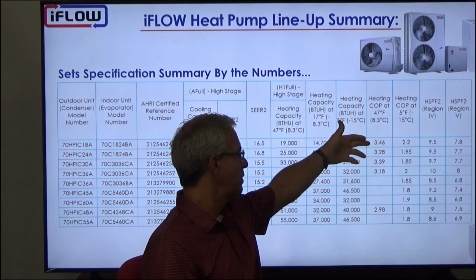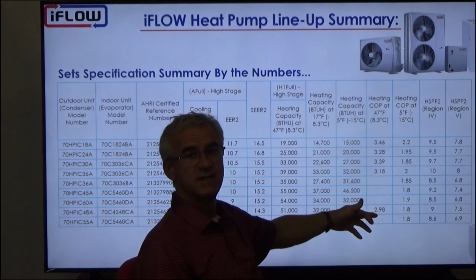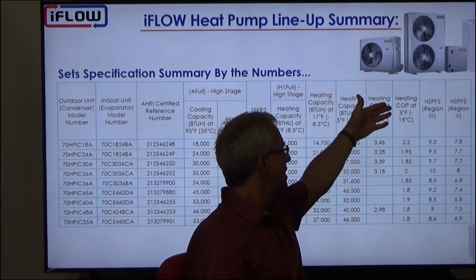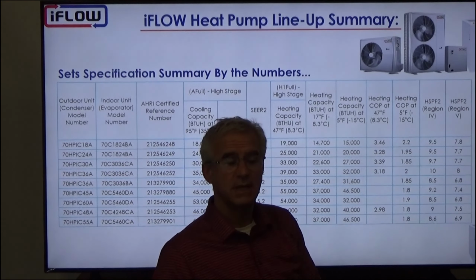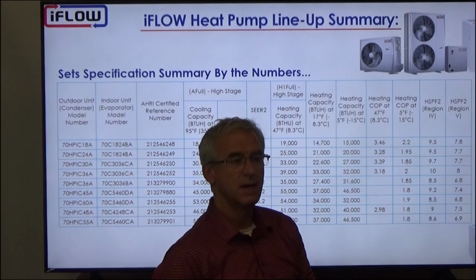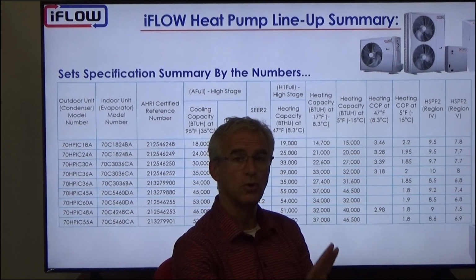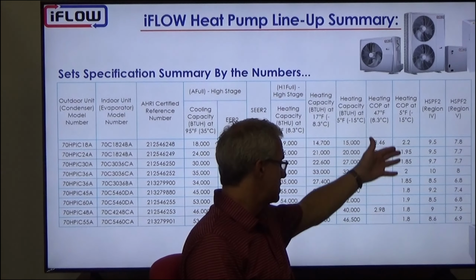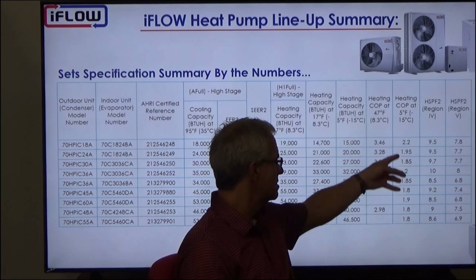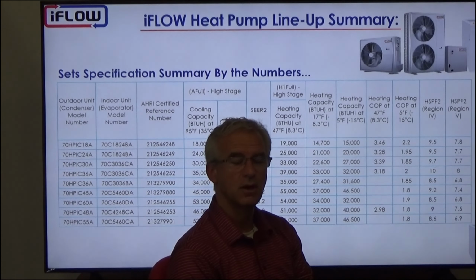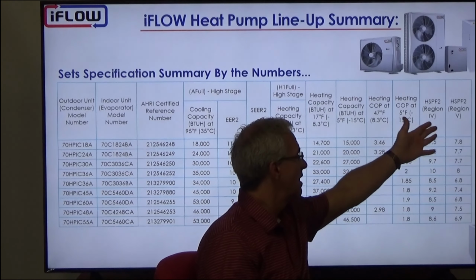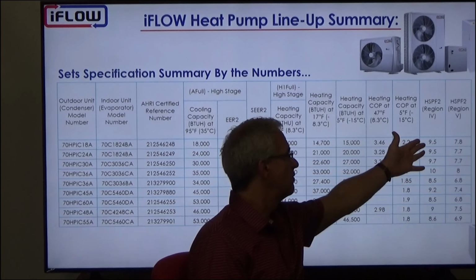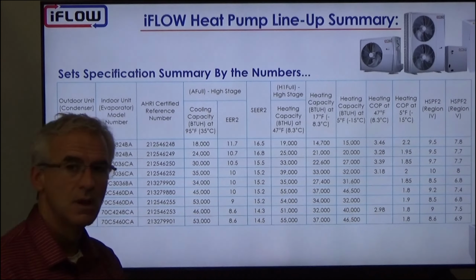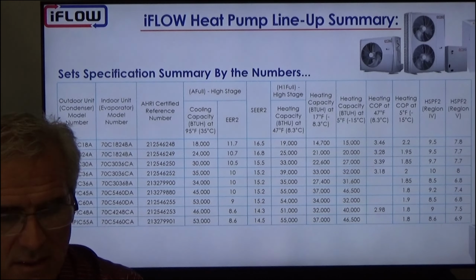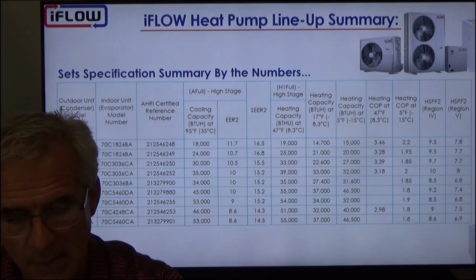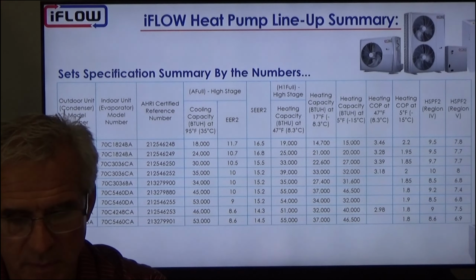So again, you see a COP of almost 3.5, right down to 3. And then as it gets colder outside, the COPs drop because the heat pump is having a harder time extracting the heat from the colder outdoor temperatures. Nonetheless, it's still close to 2 in most cases, so 200% compared to your gas-based system. And then we have the HSPF2s for Region 4 and Region 5. So those are the specifications that are listed. That's all in our literature and on our website. This is just to show you that it's there and what those numbers mean.